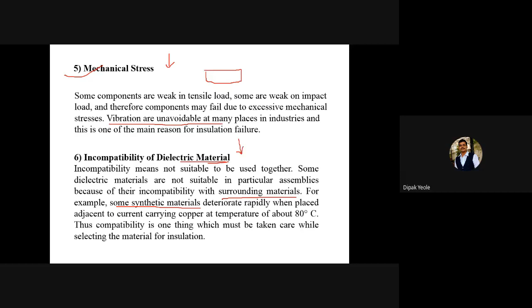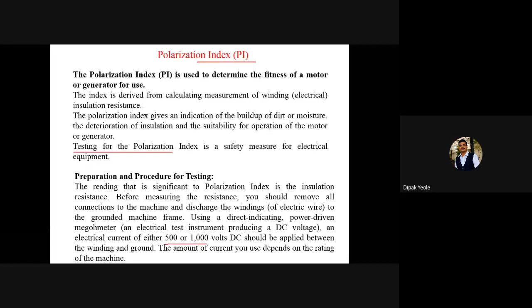Next is the concept of polarization index, and in yesterday's class we also finished the experiment on how to test the polarization index. We have to make preparations, and I told you we have to use the megohmmeter for this purpose. The ratio is the 10 minute value to the 1 minute value. The recommended value is at least 2, or greater than 2. If the polarization index is 4, it is the best material. The new equipment which we bring from the shop has a value of 4.